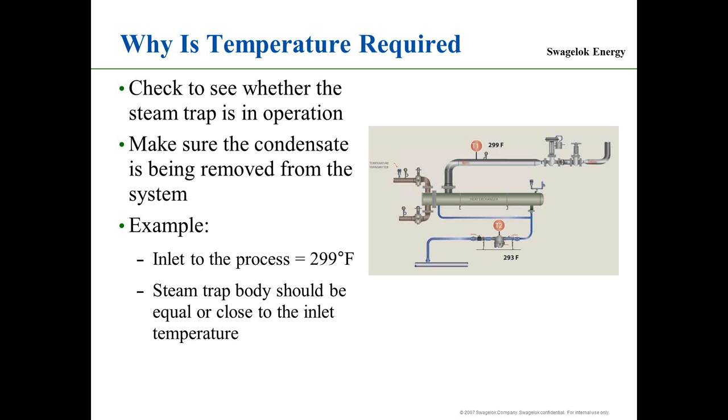So you say, you're kind of negative on temperature. No, I'm not negative on temperature. It is a tool I use, and I tell you, if you're going to go out and test steam traps, you must have temperature as part of your program. Because what I want you to do is take a temperature up here at the inlet. That temperature is 299 degrees.